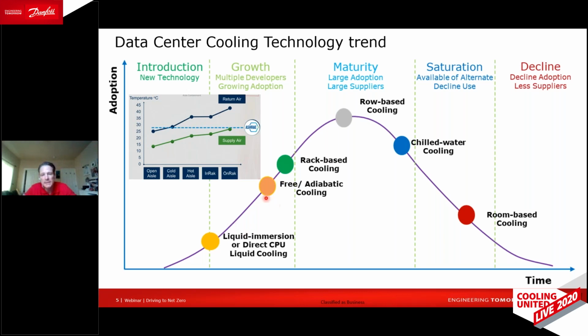But before that, that's getting closer to the equipment and higher temperature based on that sensible load. This one is based on free and adiabatic cooling on the heat rejection side, so lowering the heat rejection temperature to also increase the efficiency. And what we see is that on the air side, this is becoming much more prevalent, also on the mechanical or refrigeration side, with indirect adiabatic cooling or evaporative cooling.